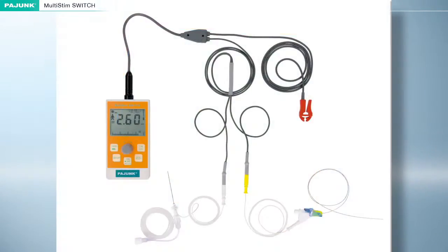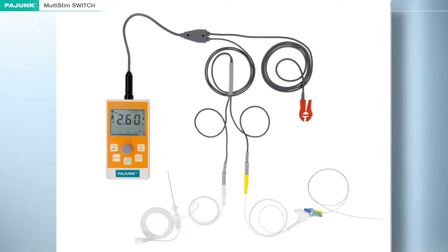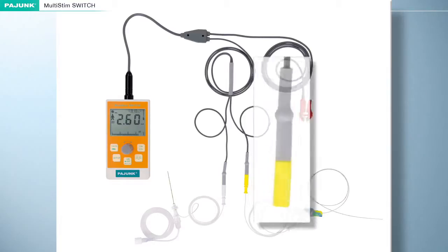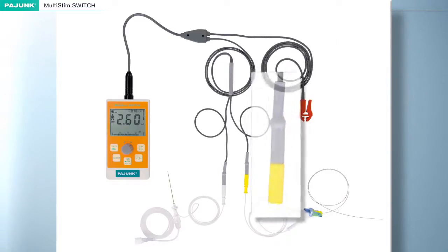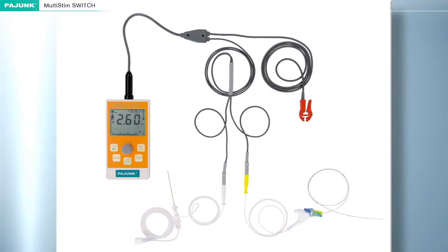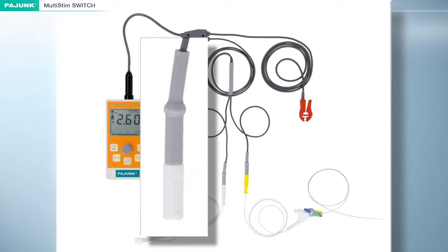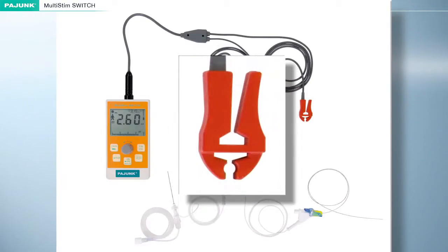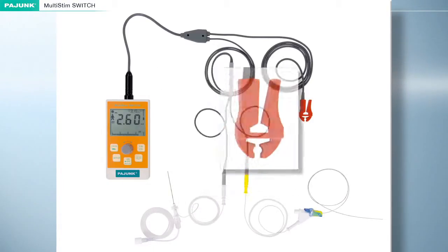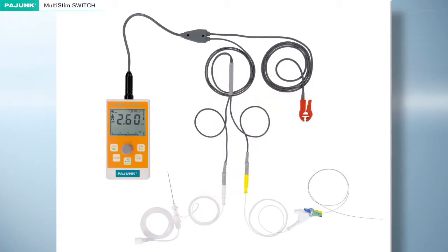The Multi-Stim Switch is simultaneously connected to the cannula and the catheter by a Y-patient cable. This cable has a yellow connector for the stimulating catheter, a white connector for the cannula, and a clamp for the adhesive electrode.